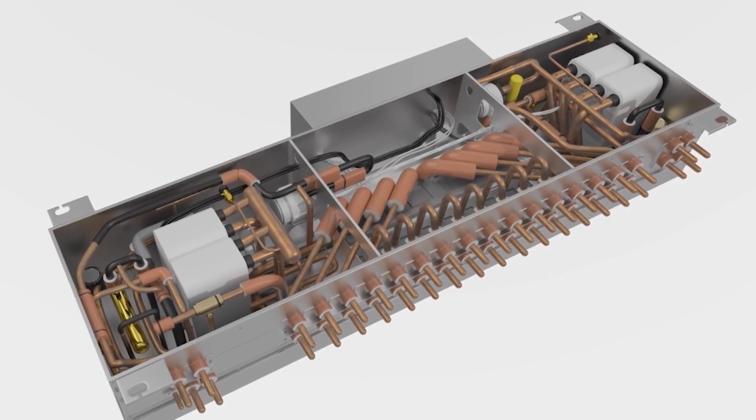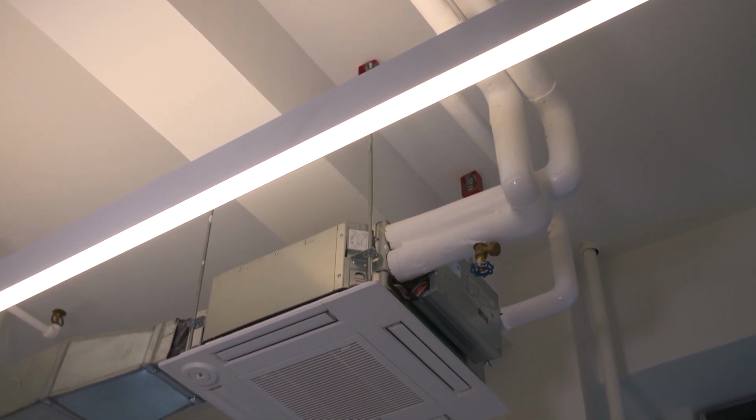Hybrid VRF is a unique two-pipe heat recovery system that replaces refrigerant with water from the indoor branch controller to the occupied space within the building, which addresses ASHRAE 15 and 34 concerns. Hybrid VRF is able to modulate refrigerant flow, fan speed, and water flow to match the loads, and it provides energy-efficient, zoned comfort. The big advantage of hybrid VRF over VRF is that there is no refrigerant in the occupied spaces. Water is actually the cooling medium or heating medium to the space, and the refrigerant is contained just between the outdoor unit and the IBC.